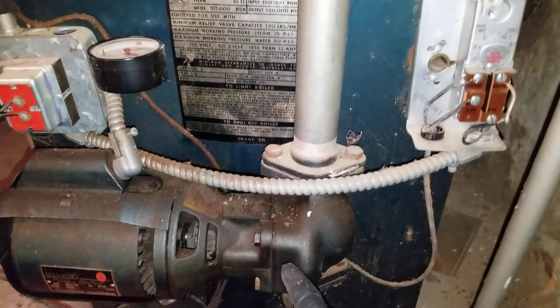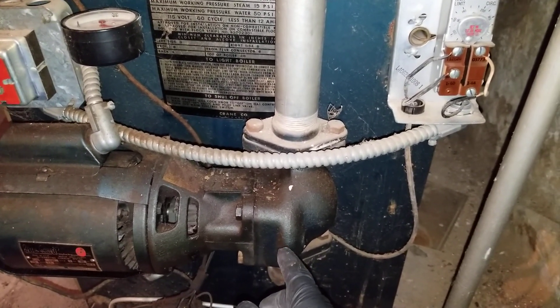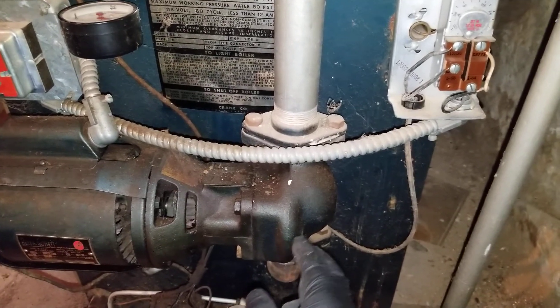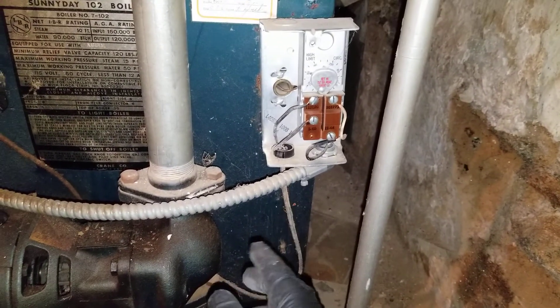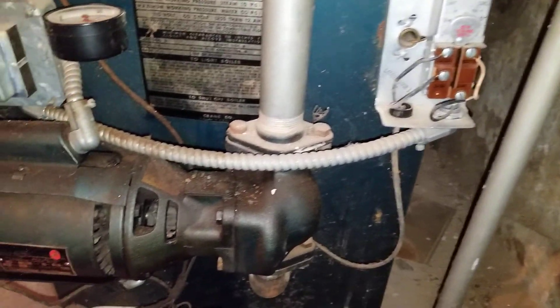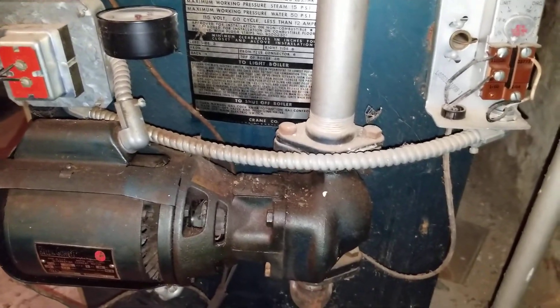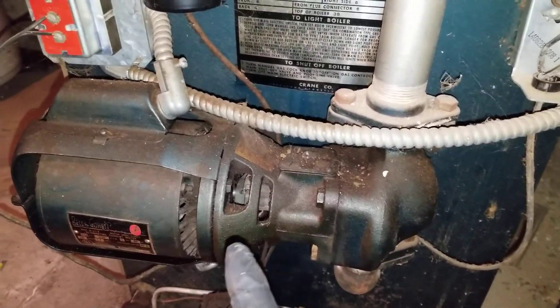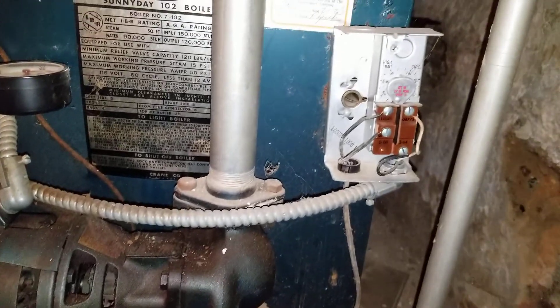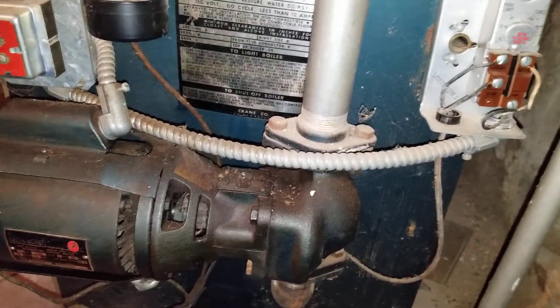The pump just started and brought cold water from the radiators, and the limit went down — the water cooled down in the boiler so the pump shut off. That way the pump does not run all the time. The question is whether it's actually good to cycle the pump on and off like this.